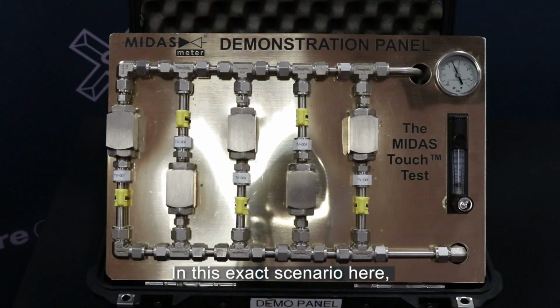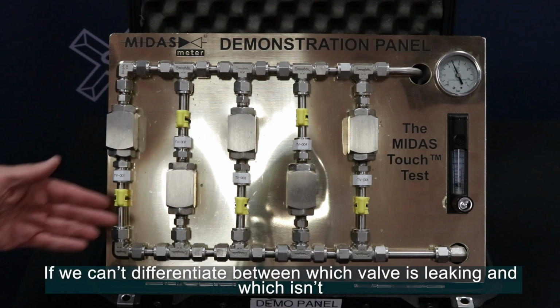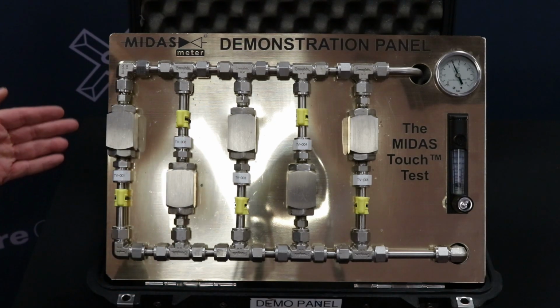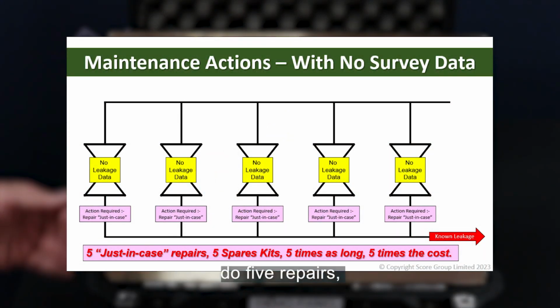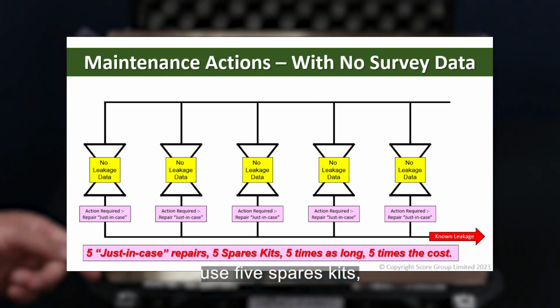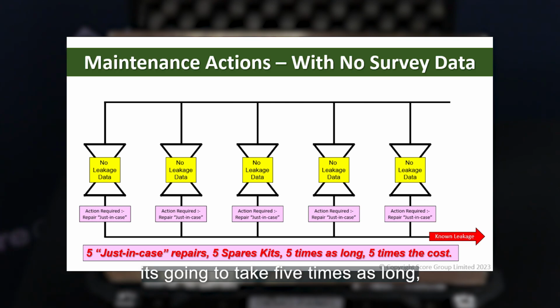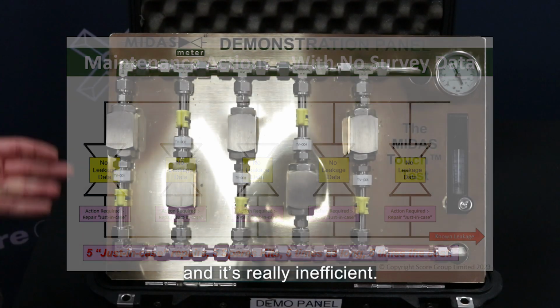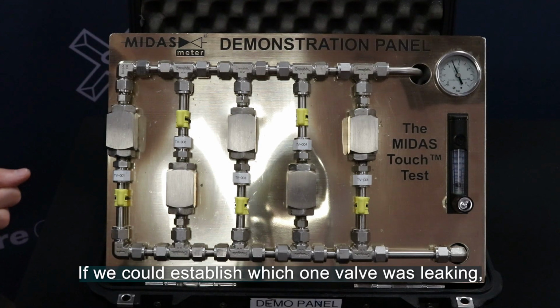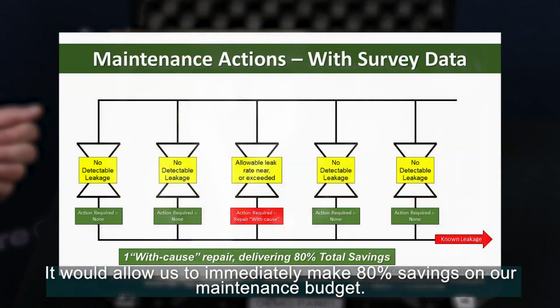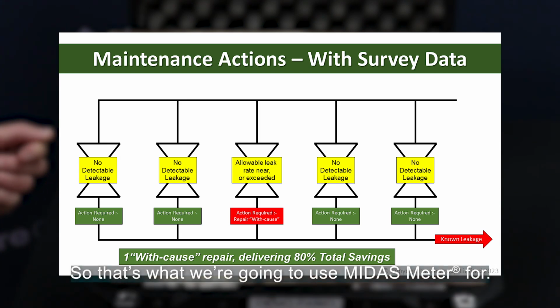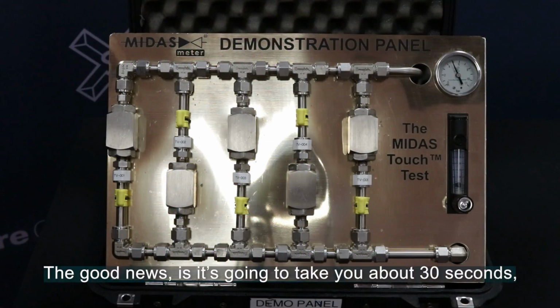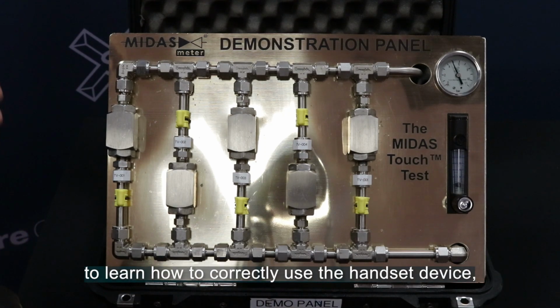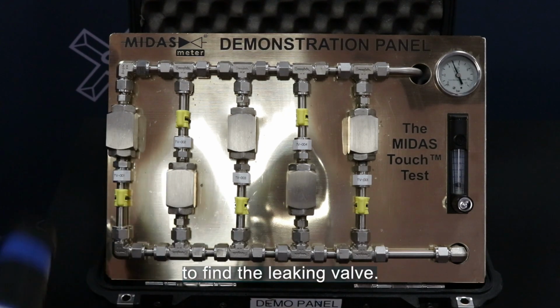In this exact scenario here, if we can't differentiate between which valve is leaking and which isn't, we're going to have to remove 5 valves, do 5 repairs, use 5 spares kits. It's going to take 5 times as long, and it's really inefficient. If we could establish which one valve was leaking, it would allow us to immediately make 80% savings on our maintenance budget. So that's what we're going to use MIDAS meter for. The good news is it's going to take you about 30 seconds to learn how to correctly use the handset device to find the leaking valve.